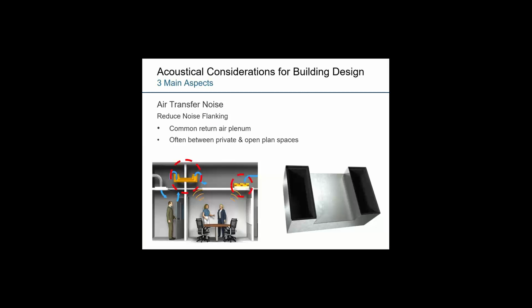Another common noise transmission path that is untreated and problematic is what we call air transfer noise, which is noise transferring from either above an occupied space or beside an occupied space. And there's many different ways of mitigating or controlling this through building design considerations like the return air openings within a ceiling, but also air transfer products like a sound boot or air transfer silencer, like a return air silencer, can work very well for this.